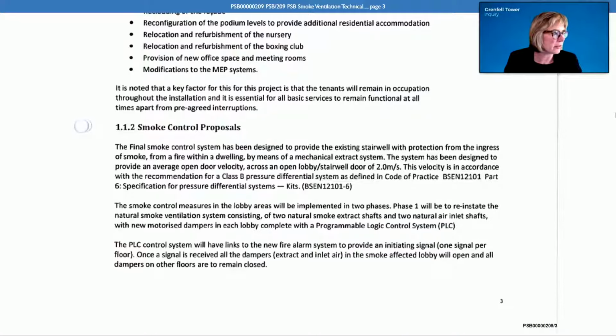we can see there that the first paragraph is as per the extract we were just looking at: the final smoke control system designed to provide the existing stairwell with protection from the ingress of smoke from a fire within a dwelling by means of a mechanical extract system. The system has been designed to provide an averaged open door velocity across an open lobby stairwell door of 2 meters per second.